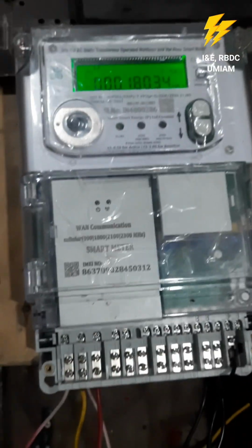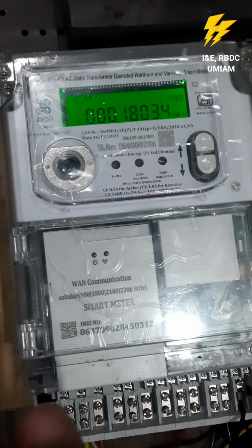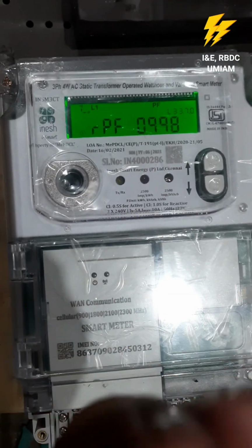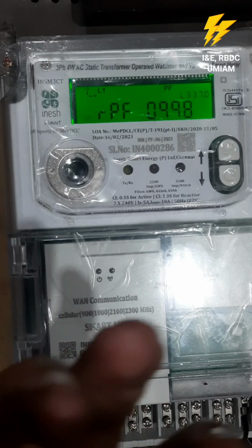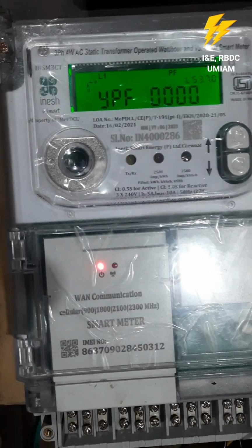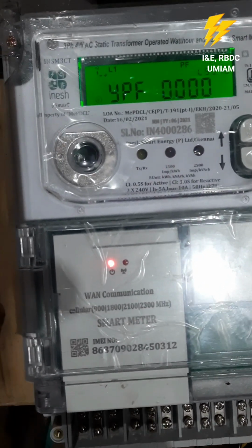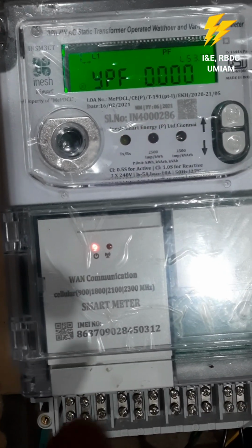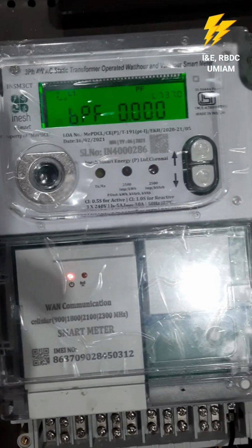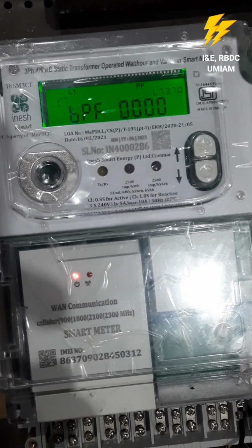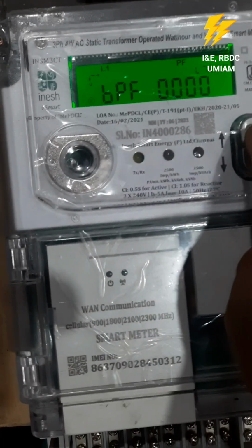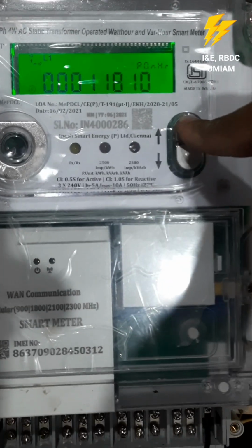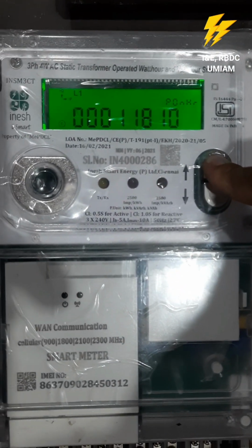And then for taking the reading of this meter, for that matter for all the LTCT meters, you will have two modes. One is the auto mode and the other is the push button mode. First of all, let us go to the auto mode. The parameters that you actually need will be available in auto mode: your present kWh, kVAh, the R phase voltage of all the phases, and the R phase current also of all the phases. For going to the auto mode, you have to keep this button, the upper button, long press.